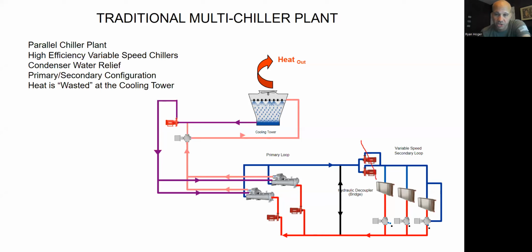So these guys would be gone, and this bridge would be gone, or might have one for just low load conditions. But conceptually, it's gone. And these circulators would be sized to handle the whole building. And you would vary these. Some chillers can handle variable water flow through them. Some chillers cannot. Same thing with boilers. So that's why we have variable primary for chillers and boilers that can handle it, and we have primary, secondary for machines that need a dedicated flow through them. So that's what's going on the chilled water side.